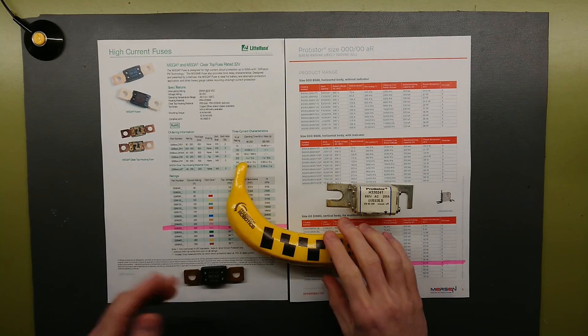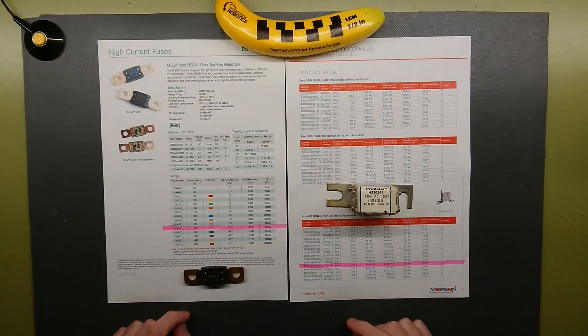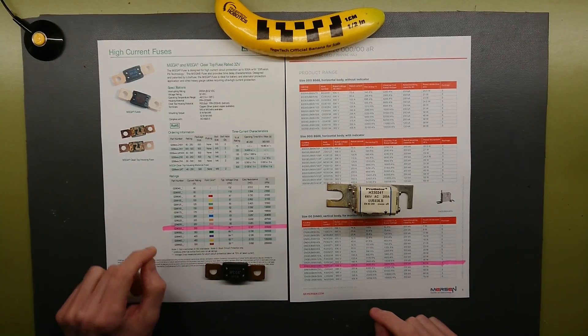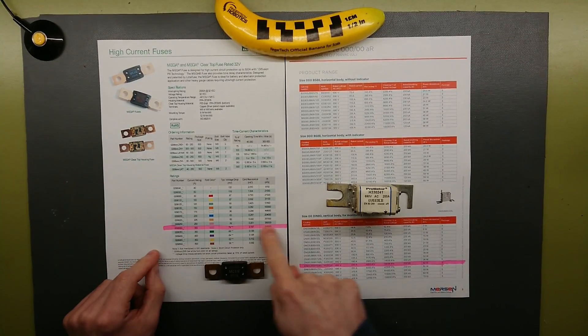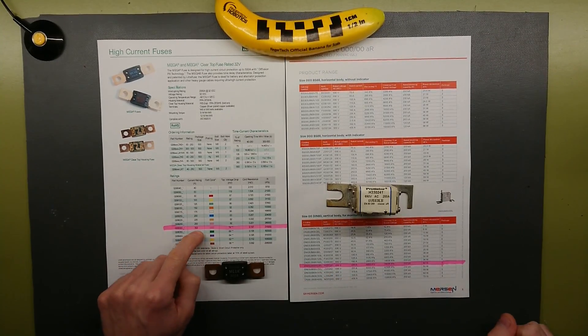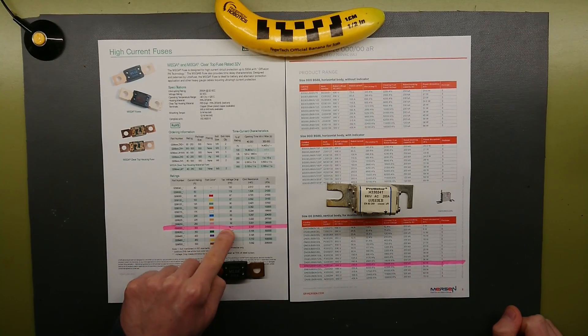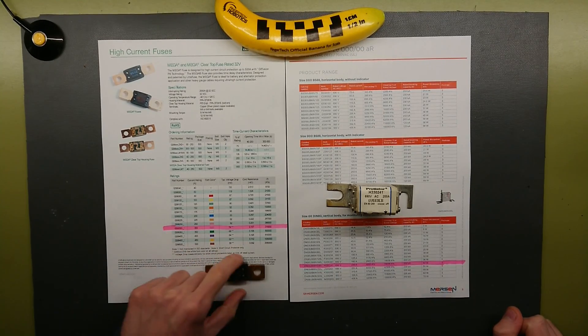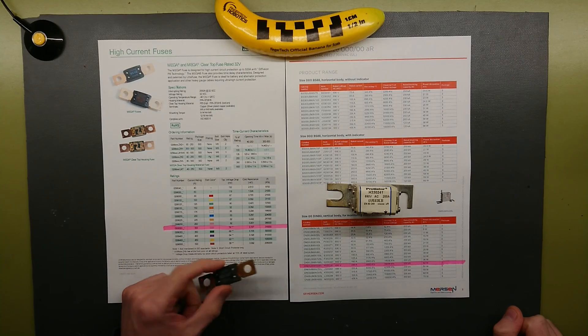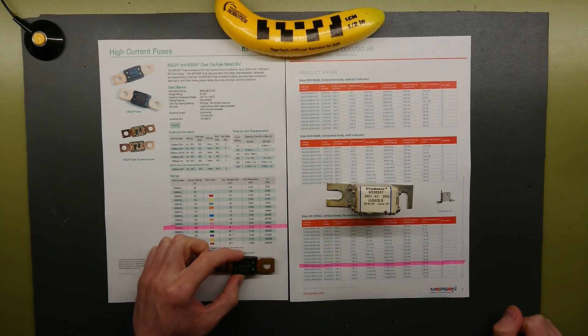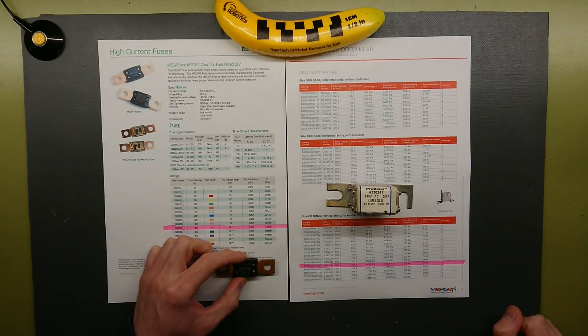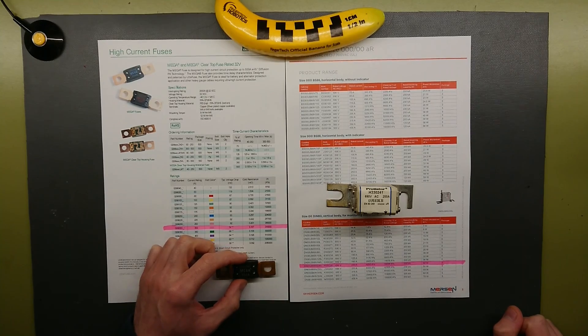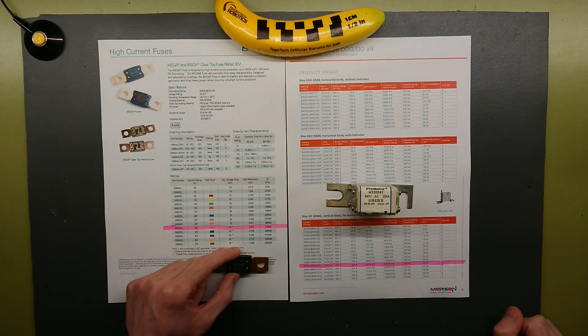If we look at the data for these two fuses, I have marked up here the 300A fuse. It has a voltage drop of 74mV at 75% rated current. This fuse has a heat dissipation of around 16W when in full operation.